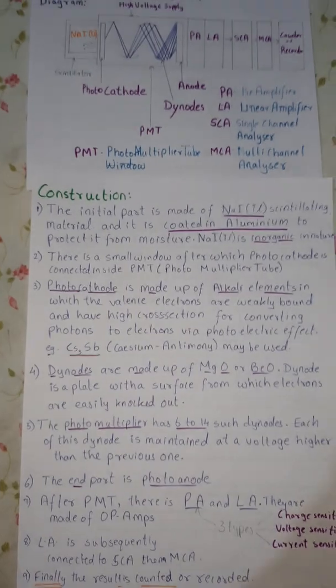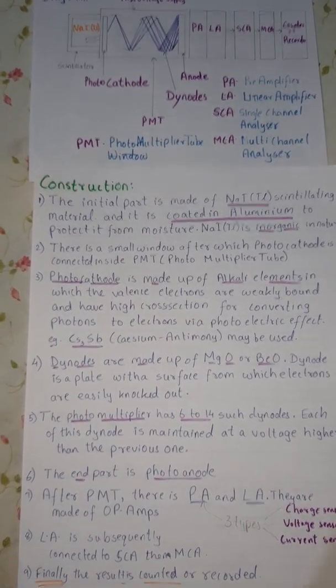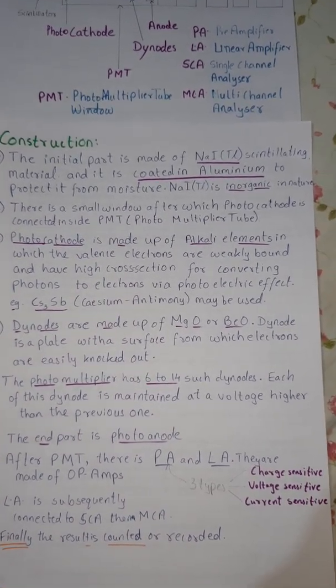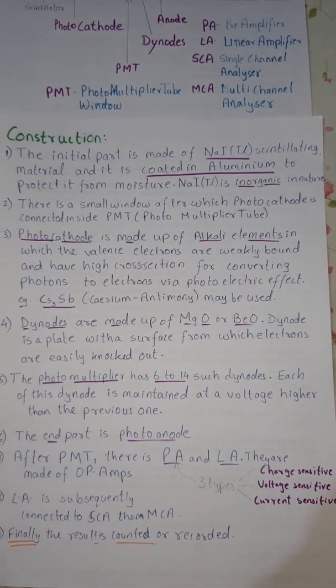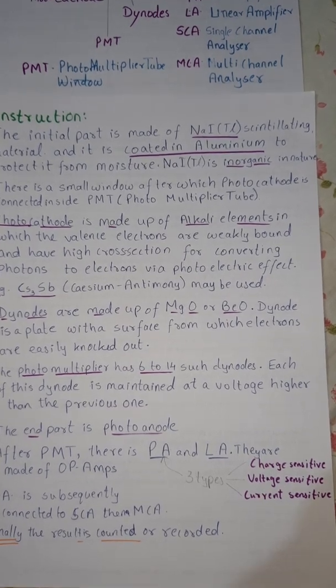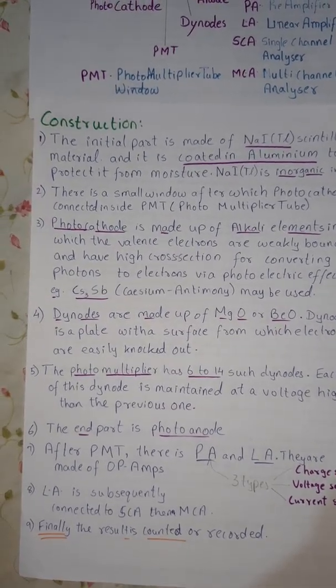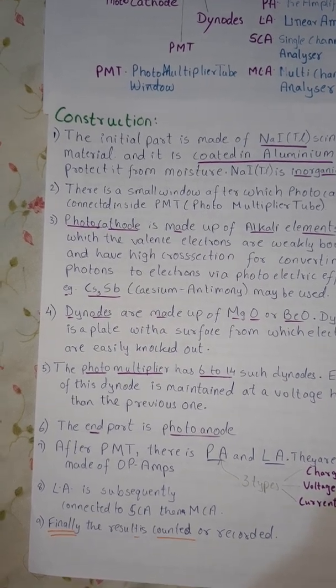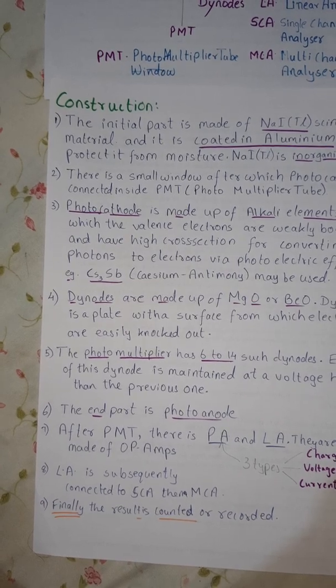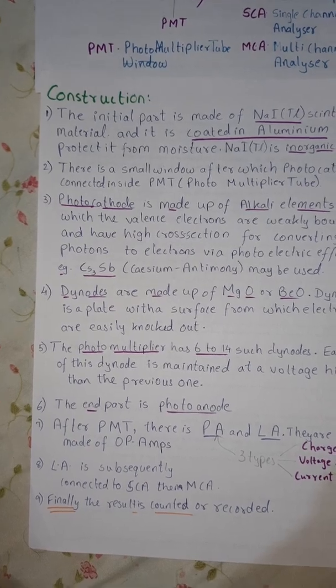The end part is photoanode. Here all the radiations are captured. After PMT there is a PA and LA. For your additional knowledge, there are three types of PA that is charge sensitive, voltage sensitive and current sensitive. These PA and LA which are amplifiers are made up of operational amplifiers. LA is subsequently connected to SCA and then MCA. In the end the result is counted or recorded.